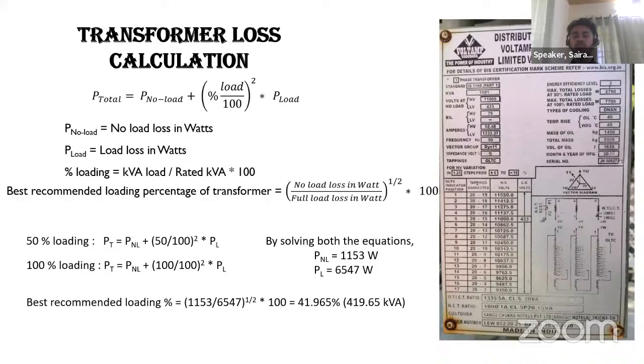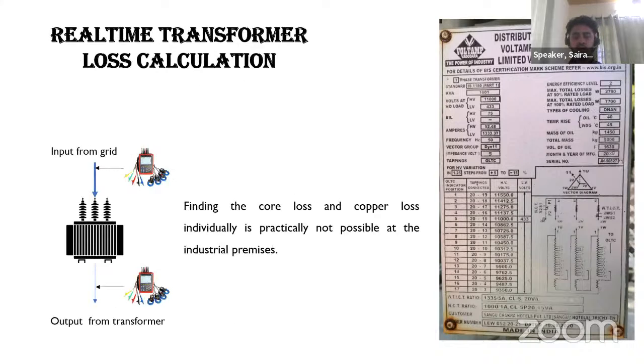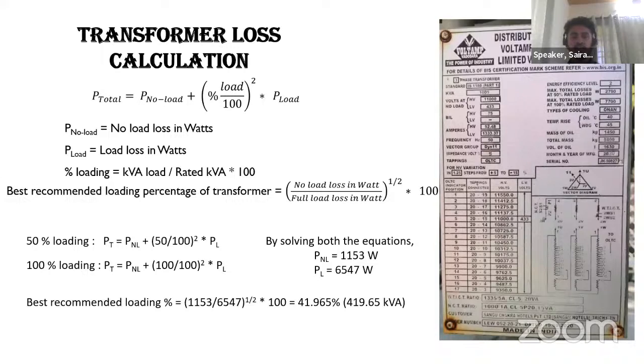If you convert it in terms of the rating, the transformer is rated at 1000 kVA. If you multiply this, you will get the best recommended loading capacity as 419.65 kVA. If you operate the transformer at this capacity, you will get better efficiency for this transformer. Practically, it is not possible to operate at the same loading point all the time. But you have to design accordingly so that most of your load patterns lie within this range of best recommended loading percentage. This is a theoretical way of calculating this.